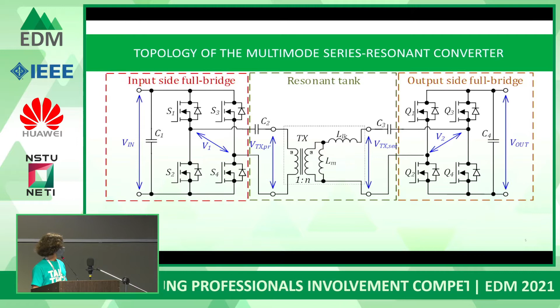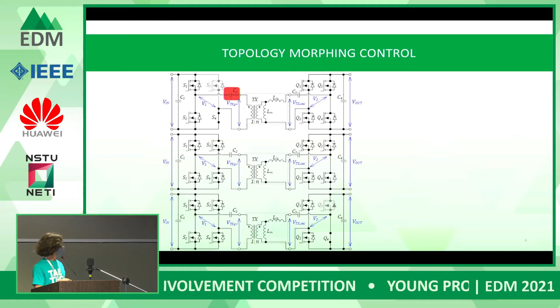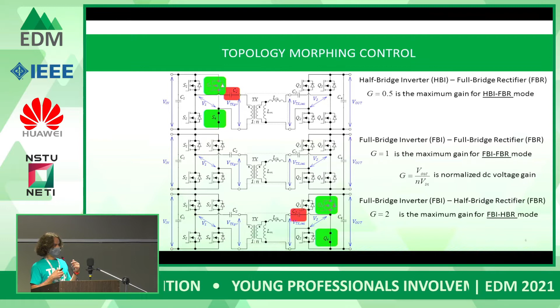The series resonant converter consists of input side and output side switching cells and a resonant tank formed based on series capacitors and an isolation transformer. The series capacitors allow for reconfiguration of full bridge cells into half bridge. Thus, the voltage gain can be changed from 1 to 0.5 or from 1 to 2, and the input voltage range can be extended.